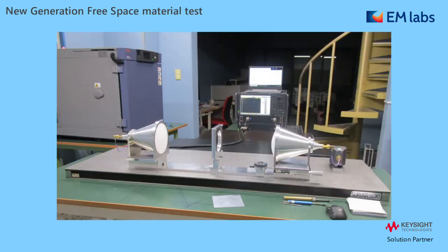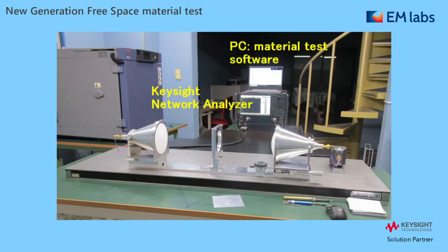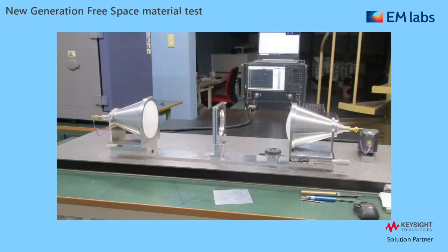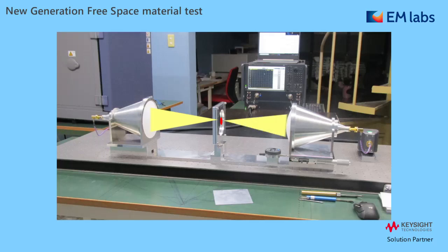With that, let's see our solution more closely. It consists of a Keysight network analyzer, a PC running the material test software, and our free space fixture. There are two lens antennas and a sample holder. The test signal is focused and applied to the material, then detected by the other antenna to analyze the signal change caused by the material.